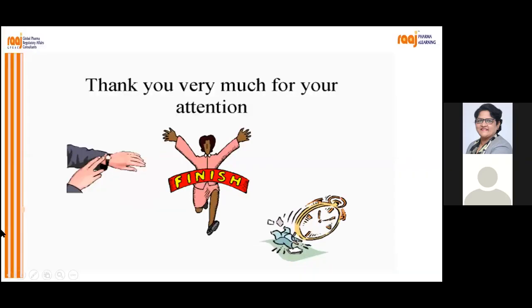All right. So this was basically regarding the SUGAM portal and everything. First of all, only manufacturers or importers can create a login ID to use the SUGAM portal. Consultants and others have not yet been given that freedom. Once you have a login, you need to make sure what type of device you manufacture, what risk classification and class your device falls into, and what checklist you have to refer to, so that you upload the device correctly.